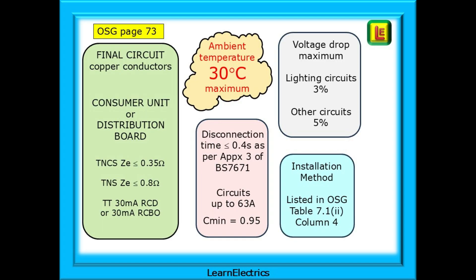We are concentrating just on Part 7.1 in this video, and even the first page of Part 7 takes some understanding, so here is an easy breakdown of page 73. The page sets out the criteria for using the tables in Part 7. It tells us that we are dealing only with final circuits with copper conductors. All circuits are assumed to start and finish - for ring circuits - at a consumer unit or distribution board.